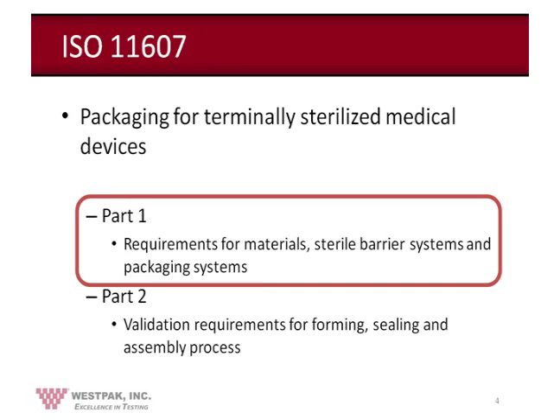ISO 11607 — Packaging for Terminally Sterilized Medical Devices — has two parts. Part one covers requirements for materials, sterile barrier system, and packaging system. Part two covers validation requirements for forming, sealing, and assembly process. WestPak follows Part one, as we are a testing laboratory that follows that section.